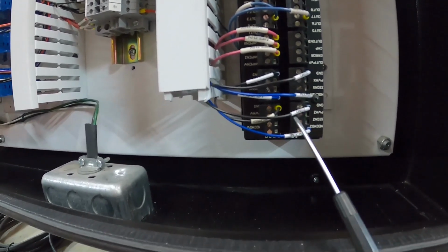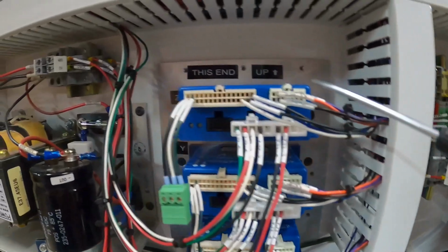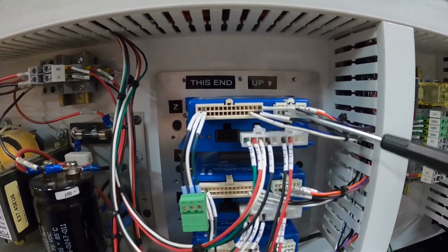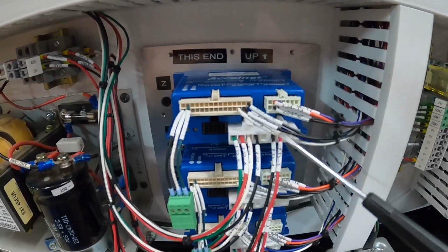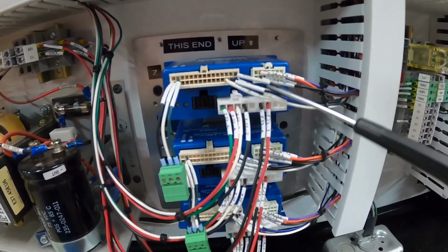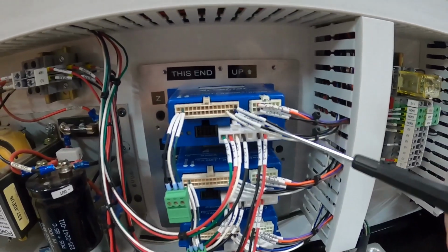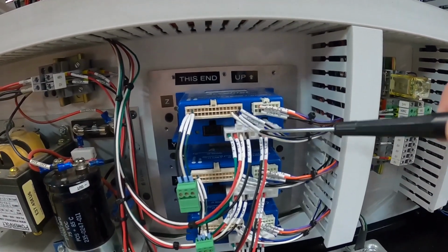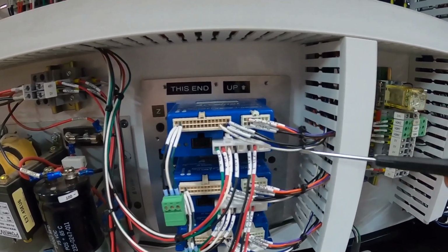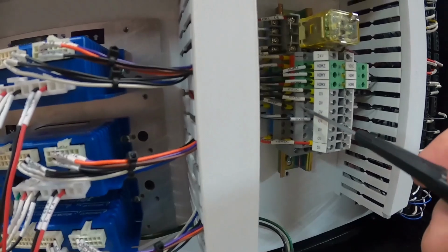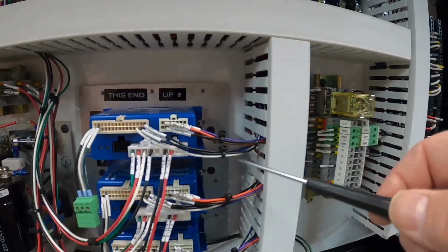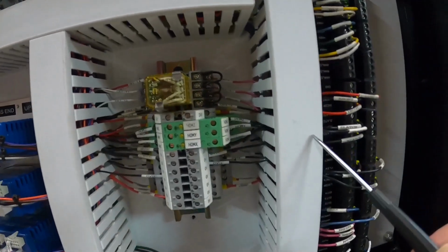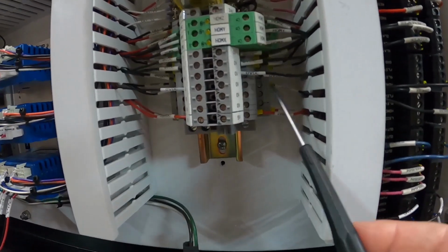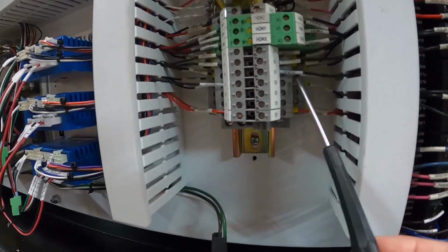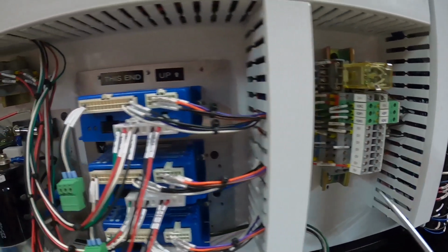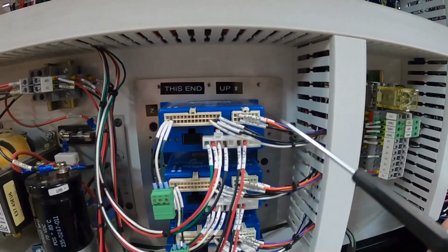It says ground Z on it, and so that ground Z goes over here to number 16 on this connector, J5. And then the blue line goes to 1 on the J5. This 0 volt line here, which is number 2, goes over to the control panel. I think it goes this way, all the way over here, and it goes in here. Z is in the back, Y is in the middle, and X is up front. So this same pattern of wires is repeated for each drive.